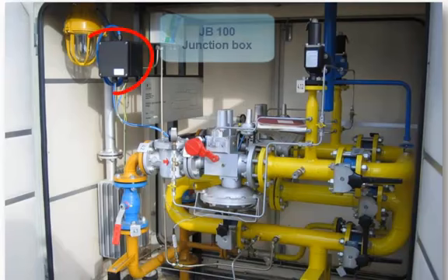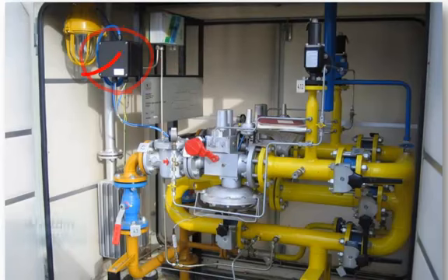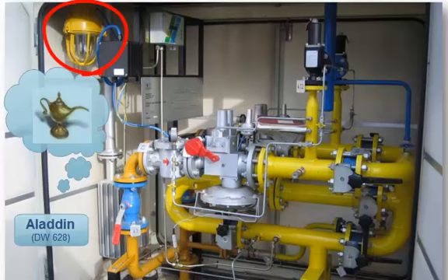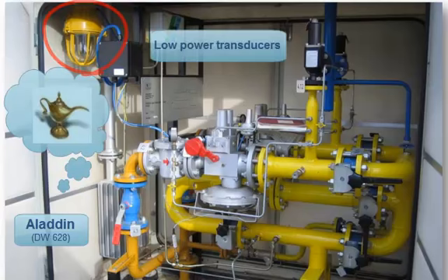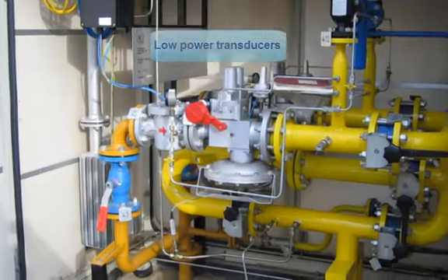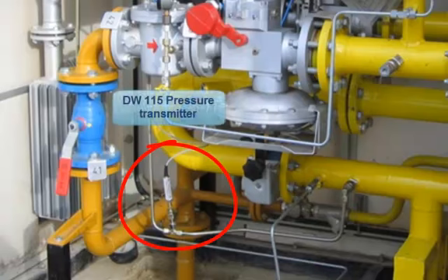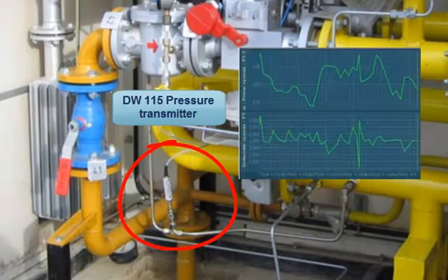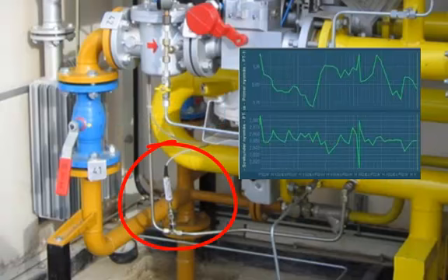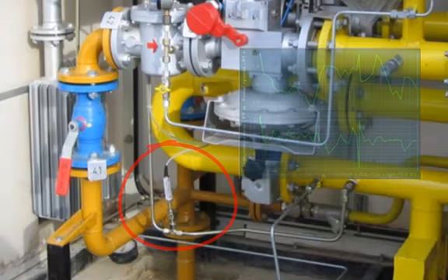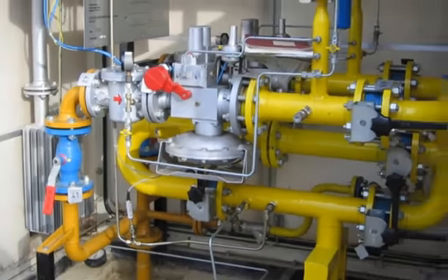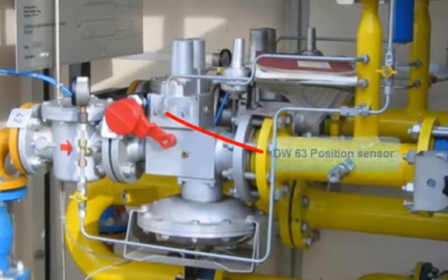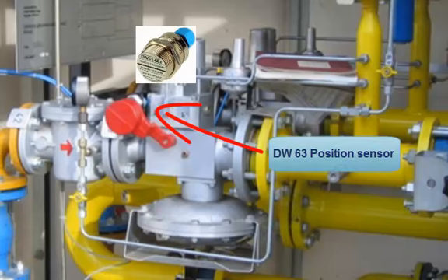The installation of the field system is quite simple. Our field controller, called Aladdin, is for collecting the process data. There are special low-power transducers installed in the cabinet. The DIWICON pressure transmitter is connected to the process by a simple T connection. Pressure transmitters are for measuring both the inlet and outlet pressures. In this case, the inlet pressure means the pressure of the transportation pipeline, while the outlet is the regulated one. The state of the pilot valve is sensed by the DIWICON position sensor. I mean sensors, because the secondary rail has the same instruments.